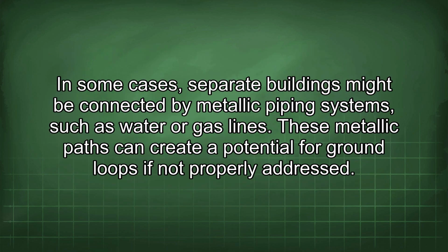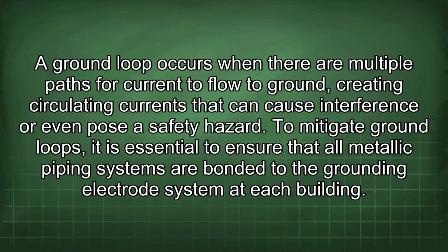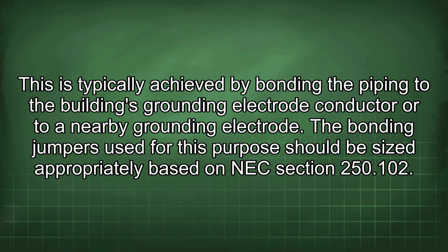In some cases, separate buildings might be connected by metallic piping systems such as water or gas lines. These metallic paths can create a potential for ground loops if not properly addressed. A ground loop occurs when there are multiple paths for current to flow to ground, creating circulating currents that can cause interference or even pose a safety hazard. To mitigate ground loops, it is essential to ensure that all metallic piping systems are bonded to the grounding electrode system at each building.